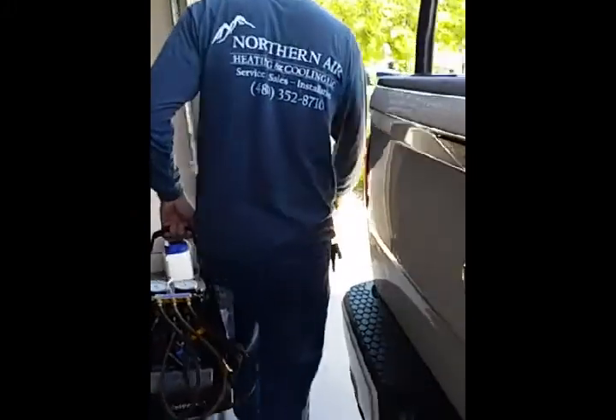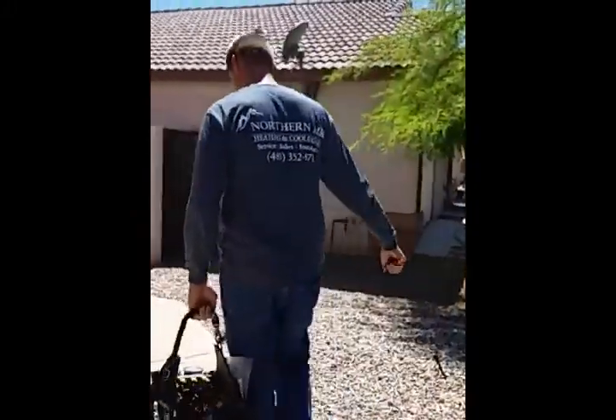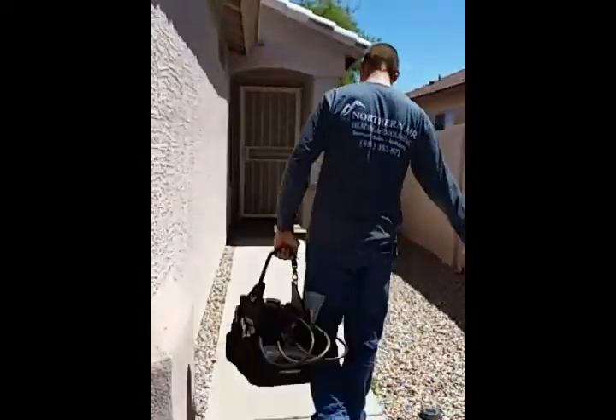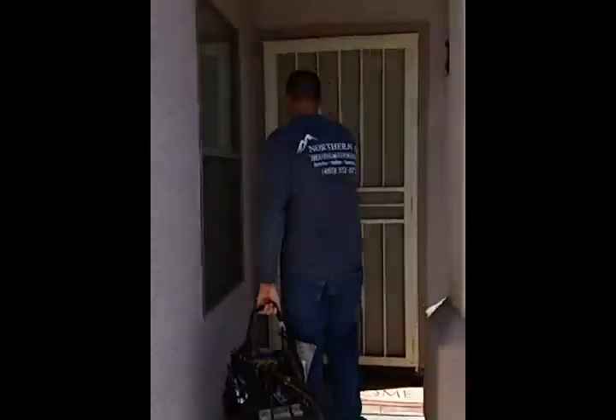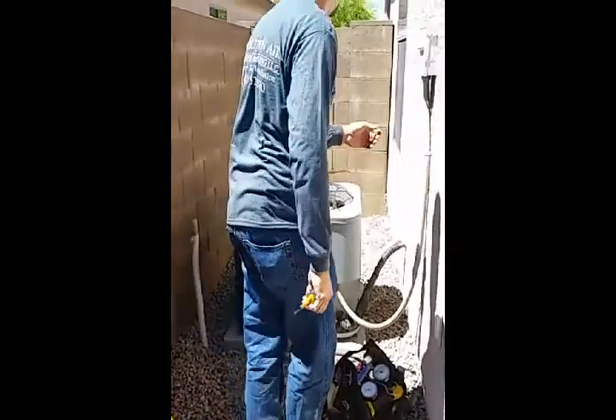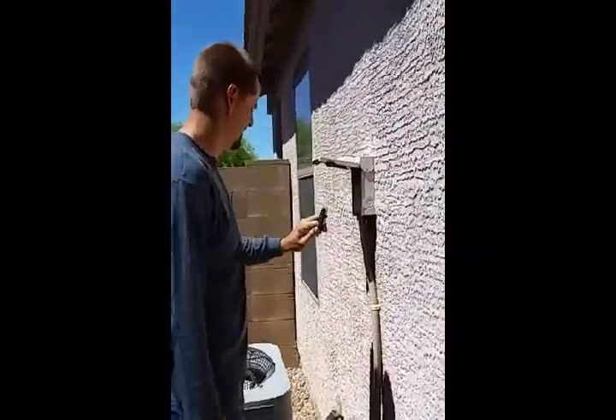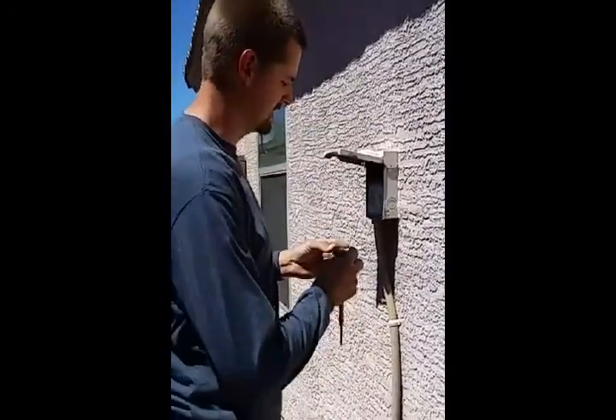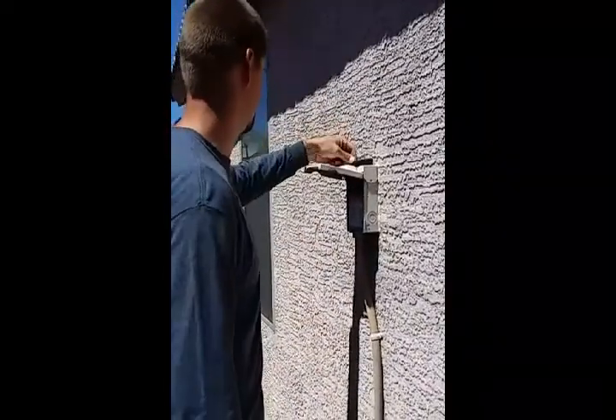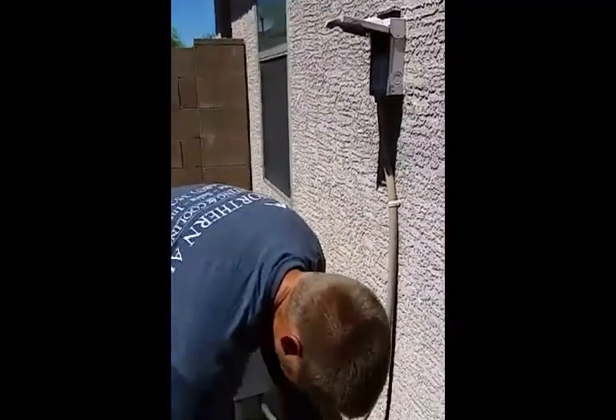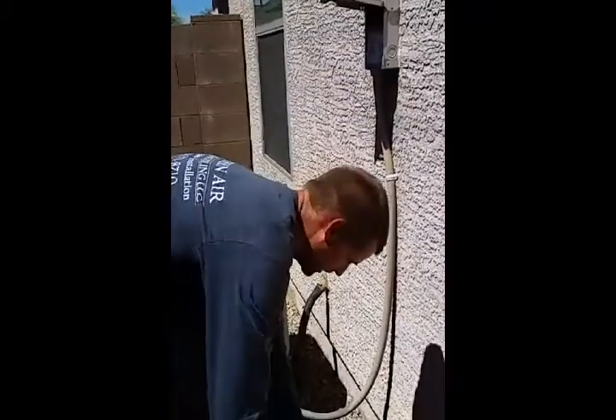Okay. So what we'll do is we'll go pull the disconnect out of the condenser. And there's our dog. Okay. Now, this is a non-fused disconnect. It isn't really what I recommend, but they do work. Like I said, we'll go inside now and make sure that the thermostat connections and the thermostat are okay. And I left my screwdriver on the kitchen counter.